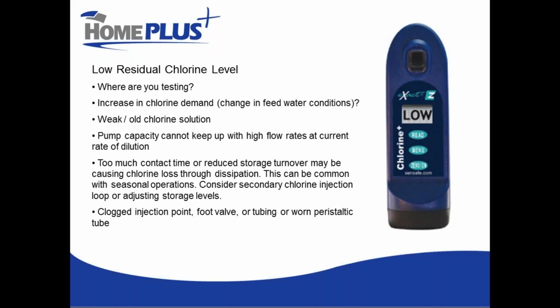You can also have a similar problem where a system has such a low flow rate relative to the water meter capabilities that were installed. So I worked on a system in Saskatchewan where there was an old mining town that used to have several hundred homes on the system. The mine had closed. There were about 15 homes remaining. They had all this huge infrastructure that was designed for high flow rates, and they were trying to run very, very low flow rates through it. Well, they had to flow about 15 or 20 gallons of water just to even register on their water meter that water was moving. So it was very hard in very low flow conditions to even activate their chlorine pump because it wouldn't get a signal from the water meter.